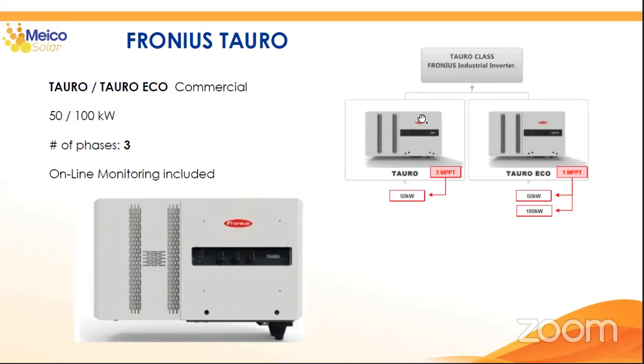With the TAURO Eco, you're going to have only 1 MPPT with powers of 50 kilowatt and 100 kilowatt. So the main difference is the type of project you're going to be installing this inverter for. If you're installing roof projects with different orientations, length of chains, and shadings, you're mainly going to use the normal TAURO because the 3 MPPTs make it easier to design and install the project. But if you're making homogeneous projects without differences in lengths and shadings, you'll mainly use the TAURO Eco with 1 MPPT, and you can go with higher power. This inverter is also 3-phase and includes built-in online monitoring.